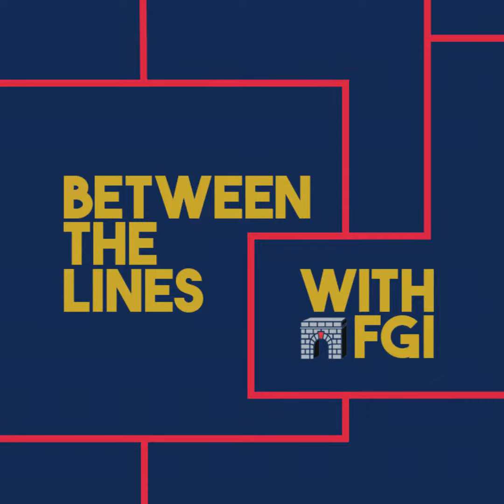So even under the best performing conditions, right, where the quench pipe works exactly as we have it designed, some of that helium gas will escape into the occupied space, right? So we want to have an exhaust system that can essentially pull that helium-rich air out of the room because it's not toxic to breathe it, but you get enough helium inside the space and it will begin to displace the breathable oxygen-rich air. And that's bad for the home team. So if we have an exhaust fan, even under the situation where everything functions exactly the way it's supposed to, we know that helium gas will get into the room and we don't want it to collect or accumulate in sufficient quantities that it starts displacing the breathable air. So we want an exhaust vent to try and get it out of there.